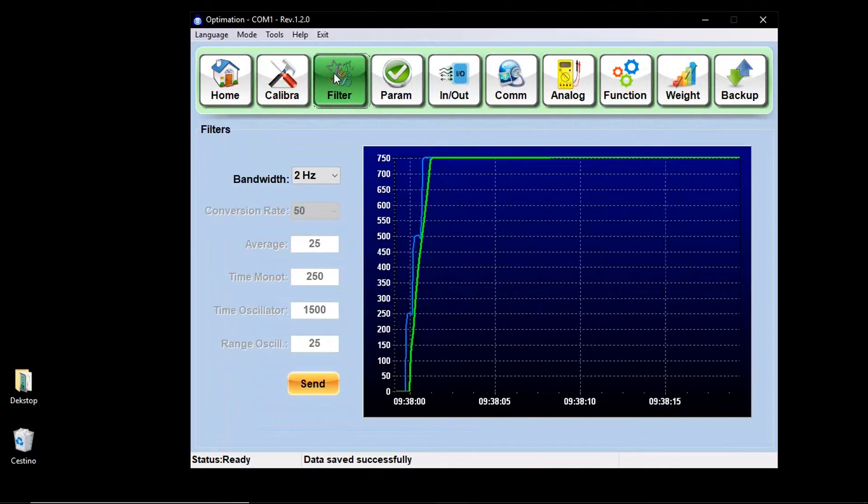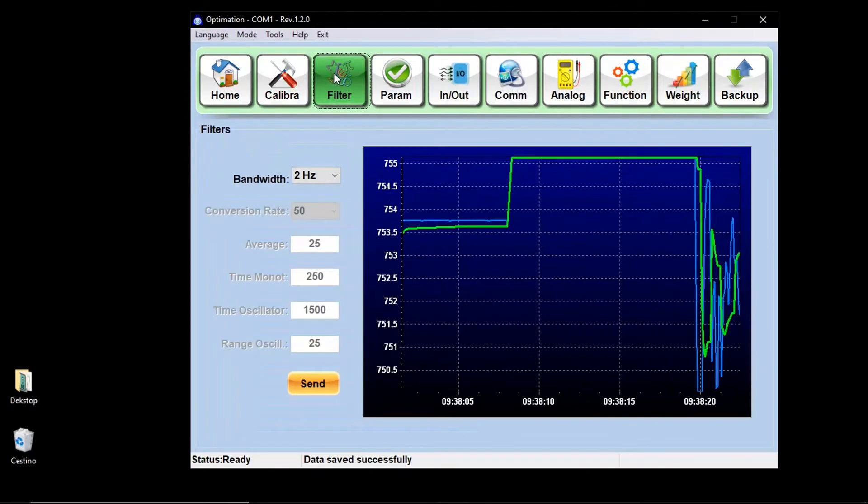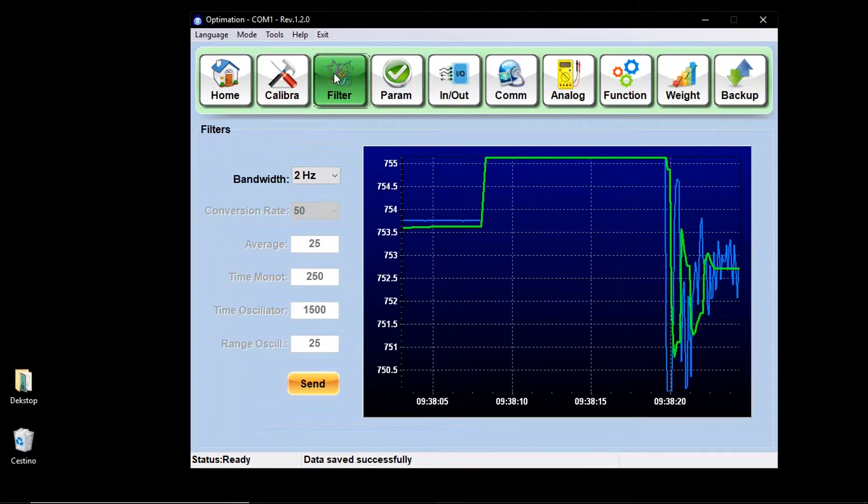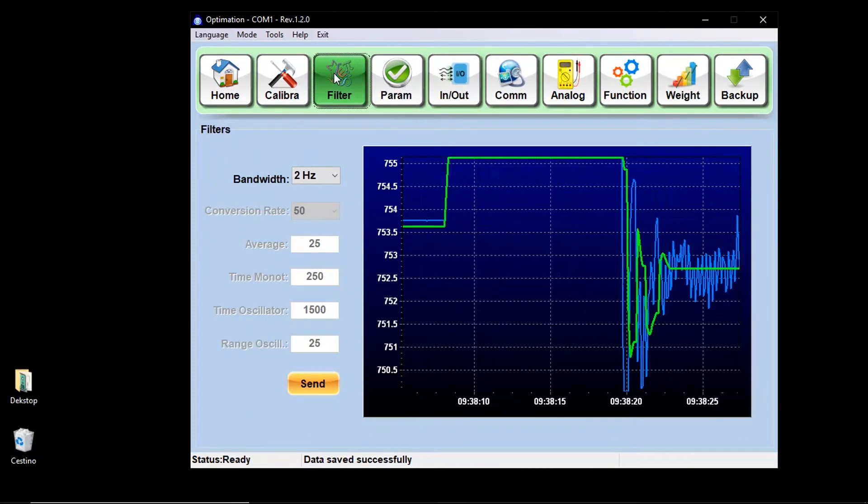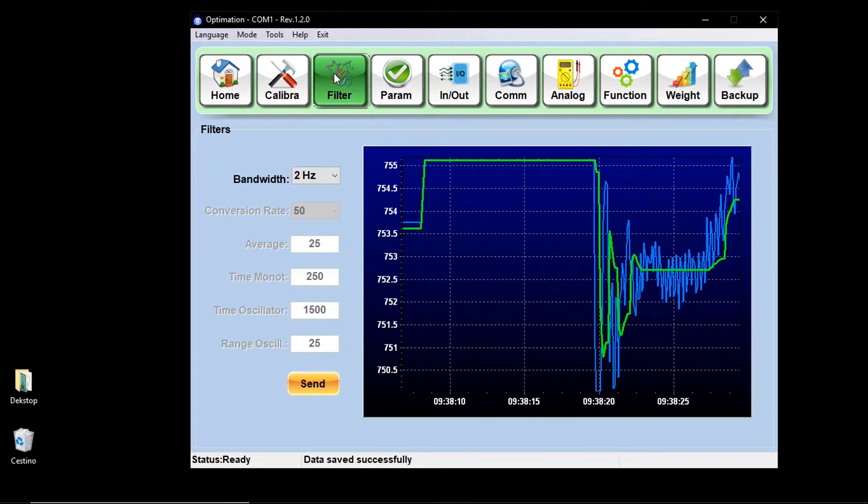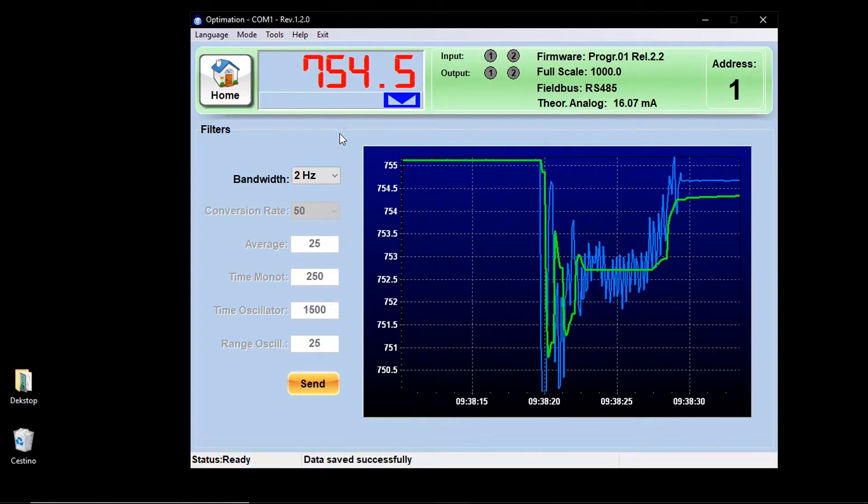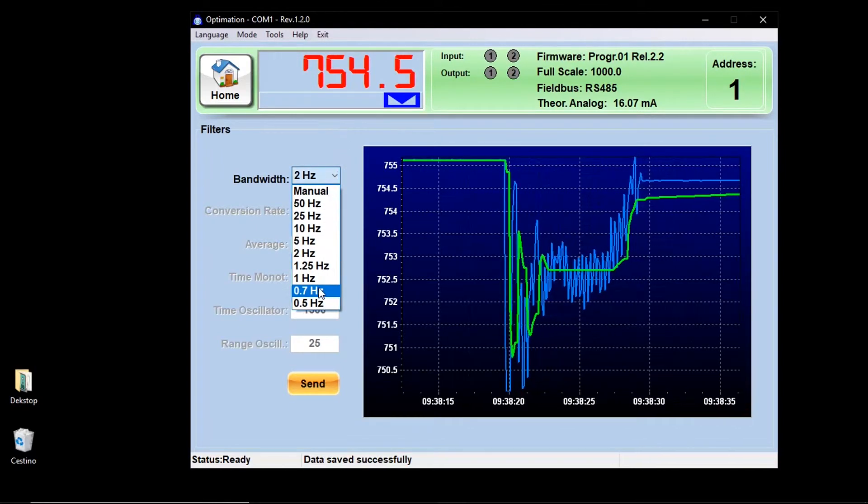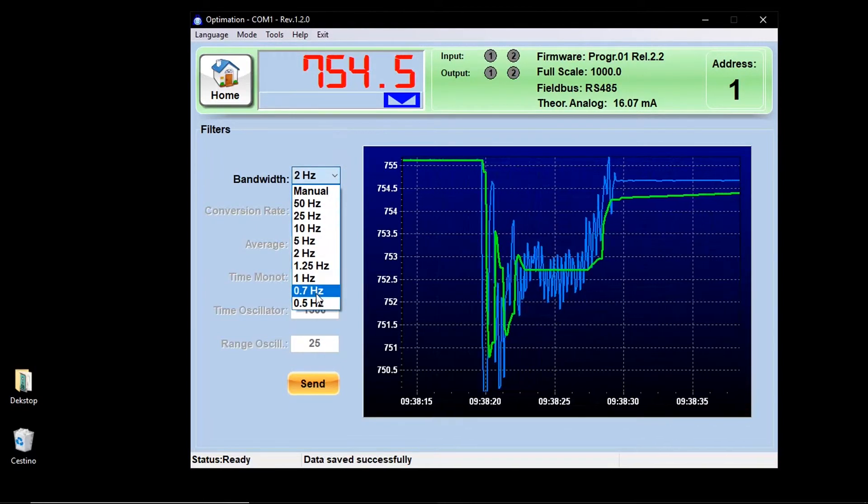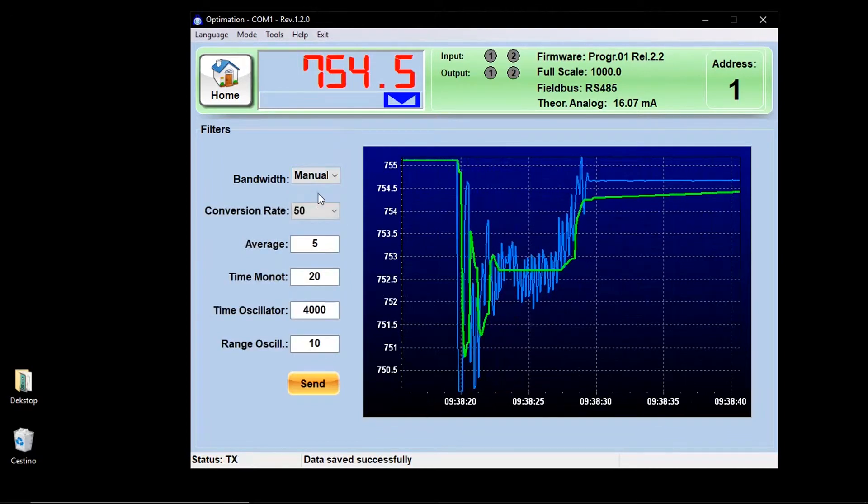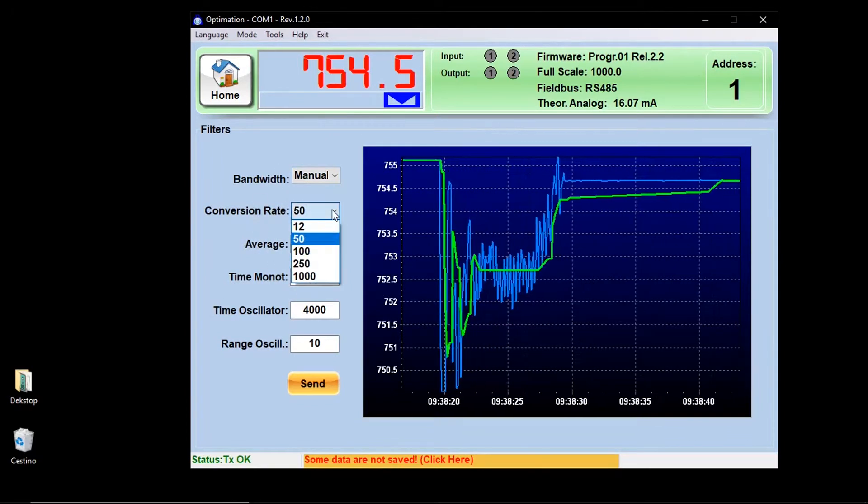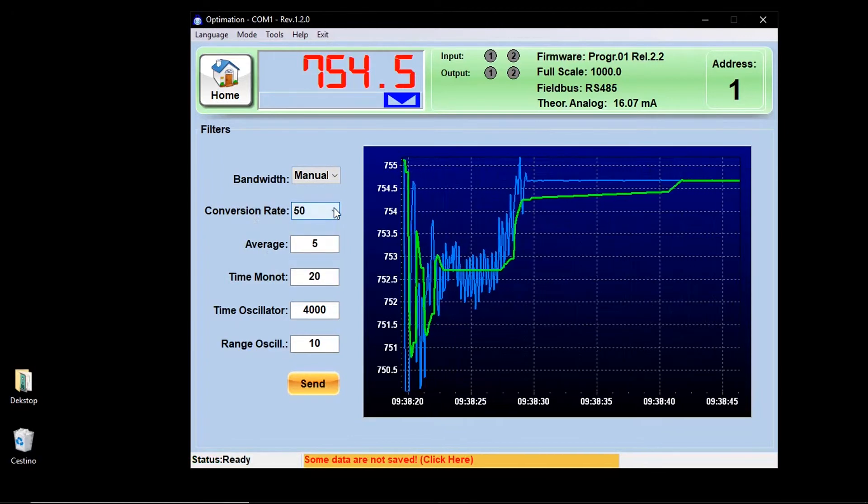By selecting the filter function key, you access the filter management of the instrument. In the screen, you will find a dynamic graph where you can see the unfiltered weight in blue and the effect that the selected filter has on the system in green. On the left side, instead, you will find the selection of the filter, where you can choose among ten preset values or select the manual function and unlock all the parameters below.